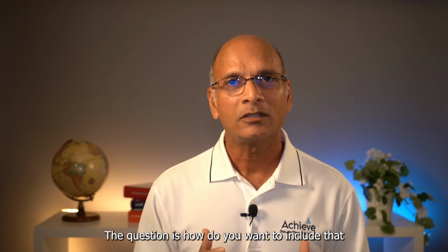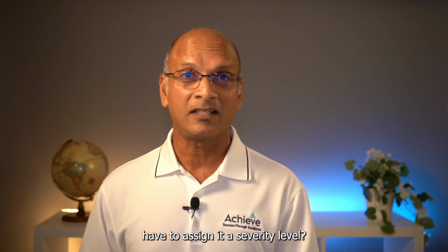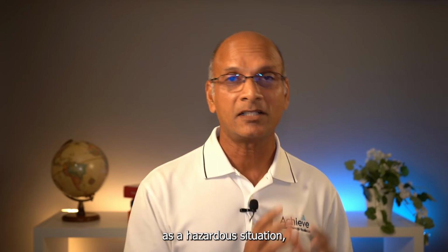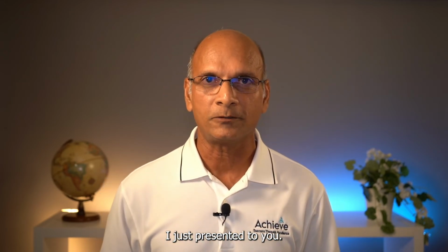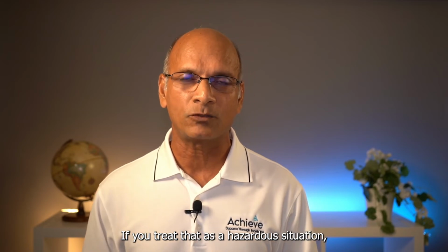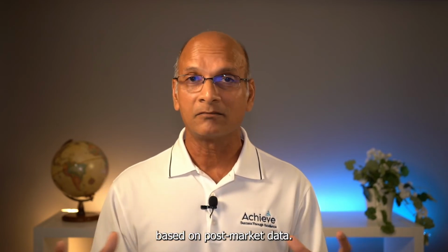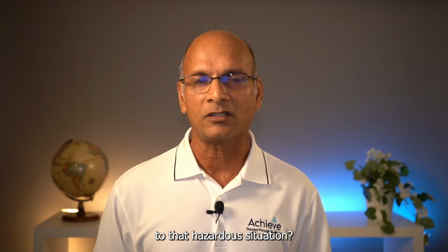But how? The question is how? Do you want to include that as a harm, which means that you have to assign it a severity level? Or do you want to look at it as a hazardous situation, which is what I was talking about in the slides I just presented to you. If you treat that as a hazardous situation, you can look up factors. You can investigate based on post-market data. What are the factors contributing to that hazardous situation?